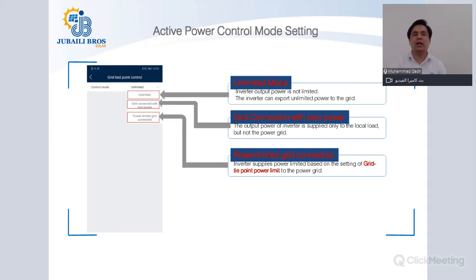So now under the export control, you will have three different ways. One way is the unlimited mode, which is normally the case of every inverter, being set as unlimited mode by default from the factory. The next one is grid connection with zero export. So you have an option of that. The third option is power limited grid connection. We will speak of all these, zero export power and also the power limited grid connection, in the next slide.